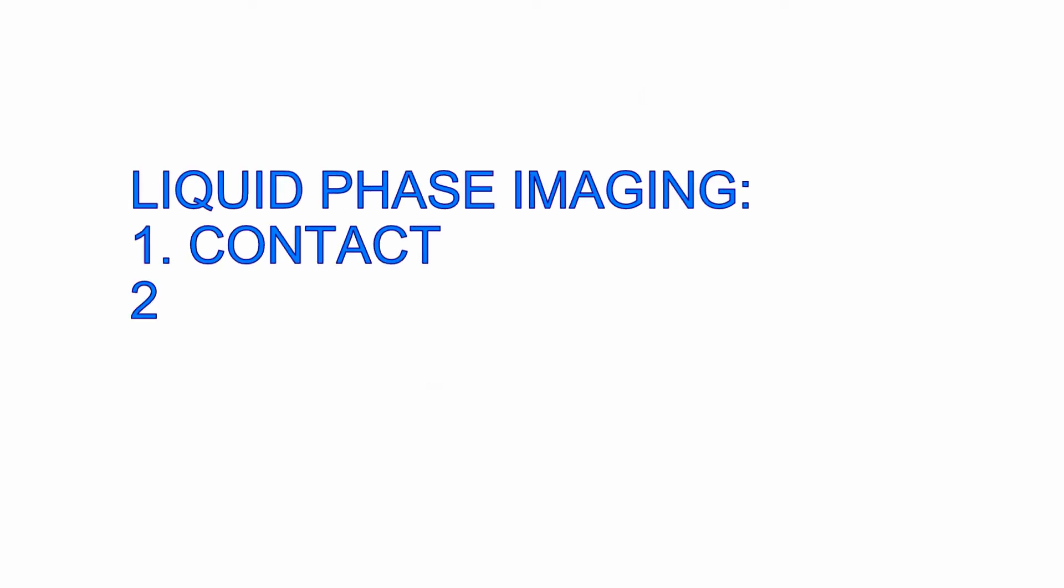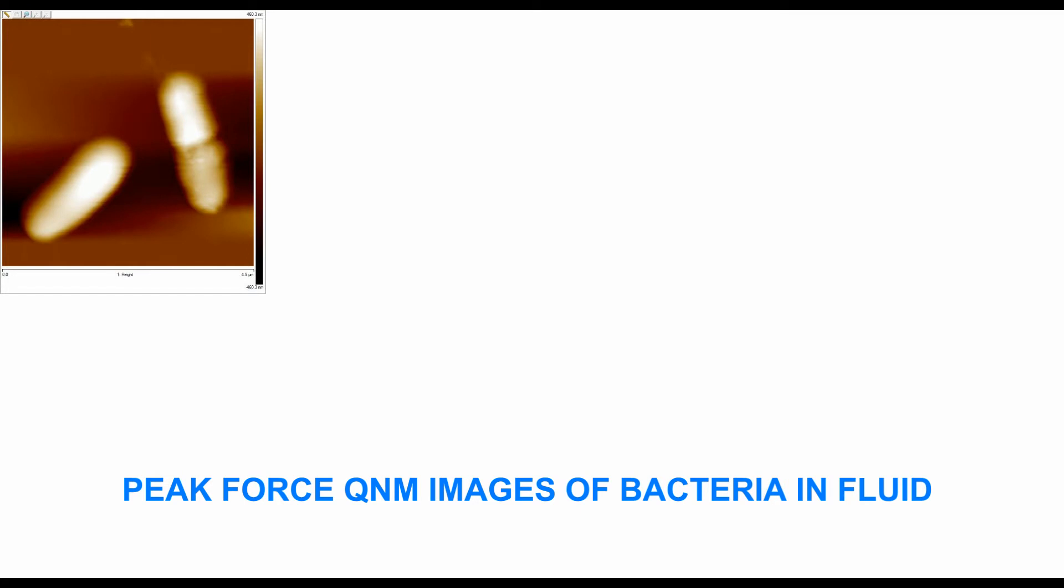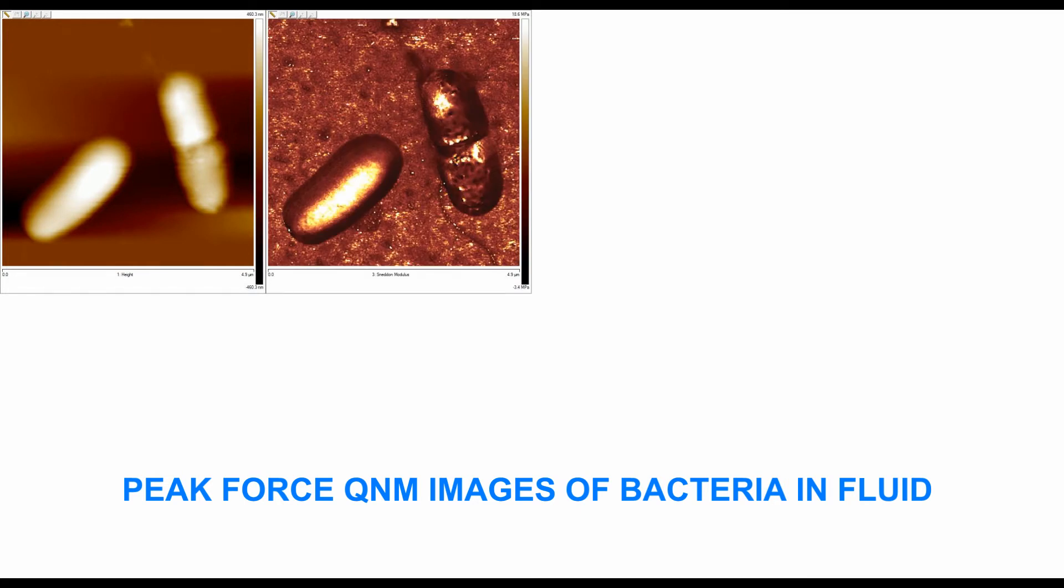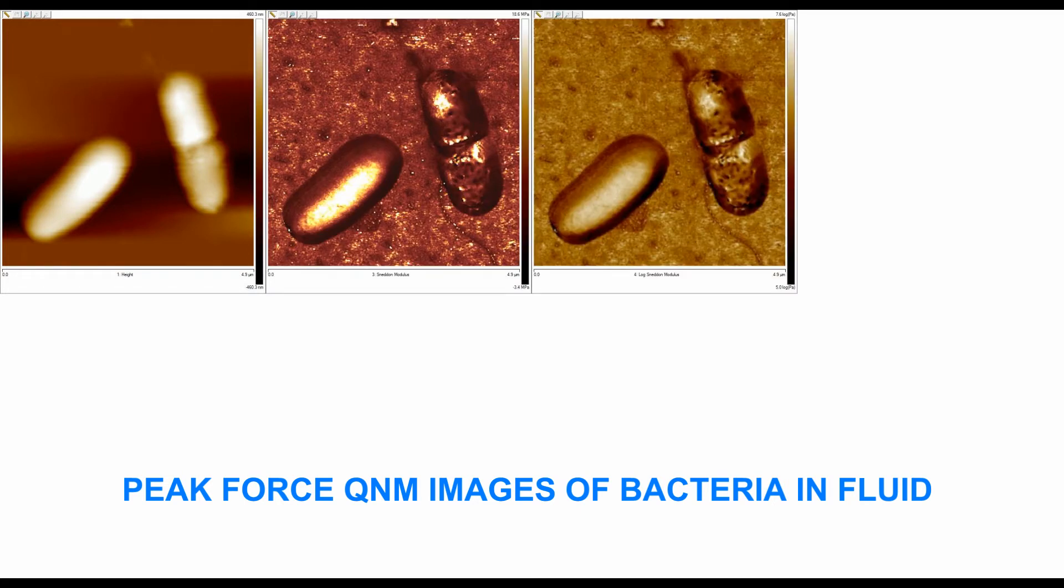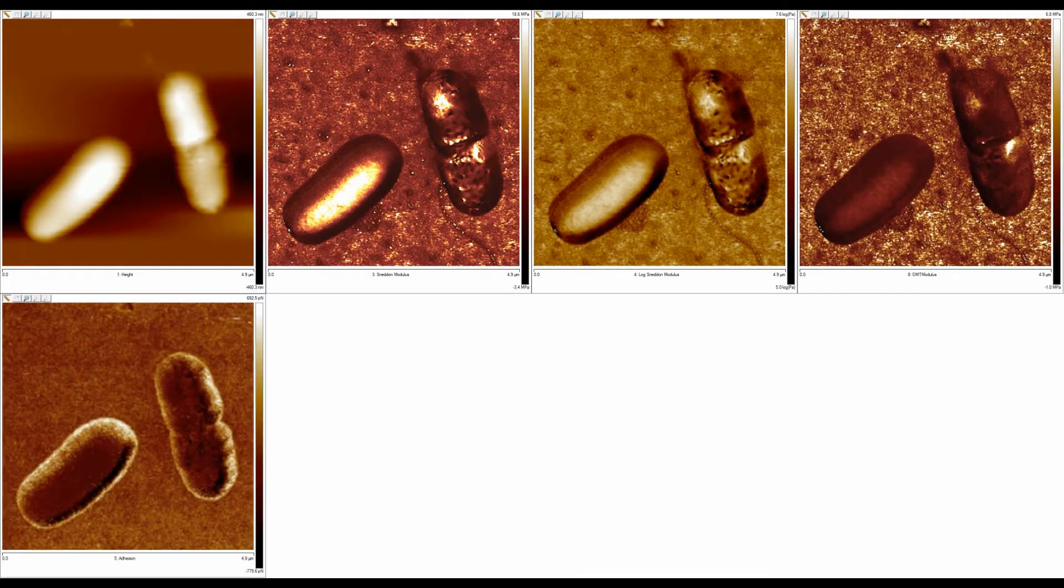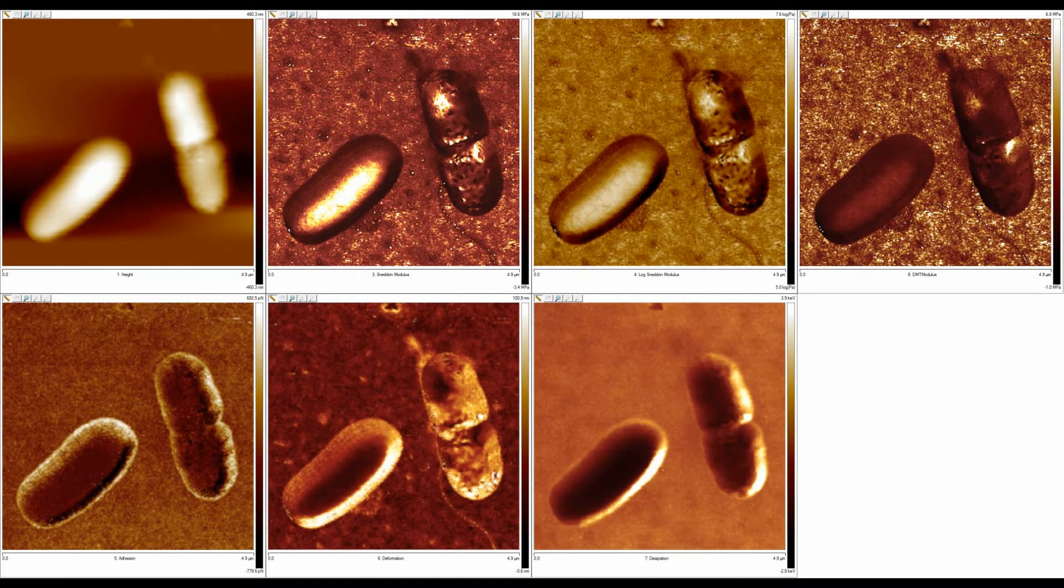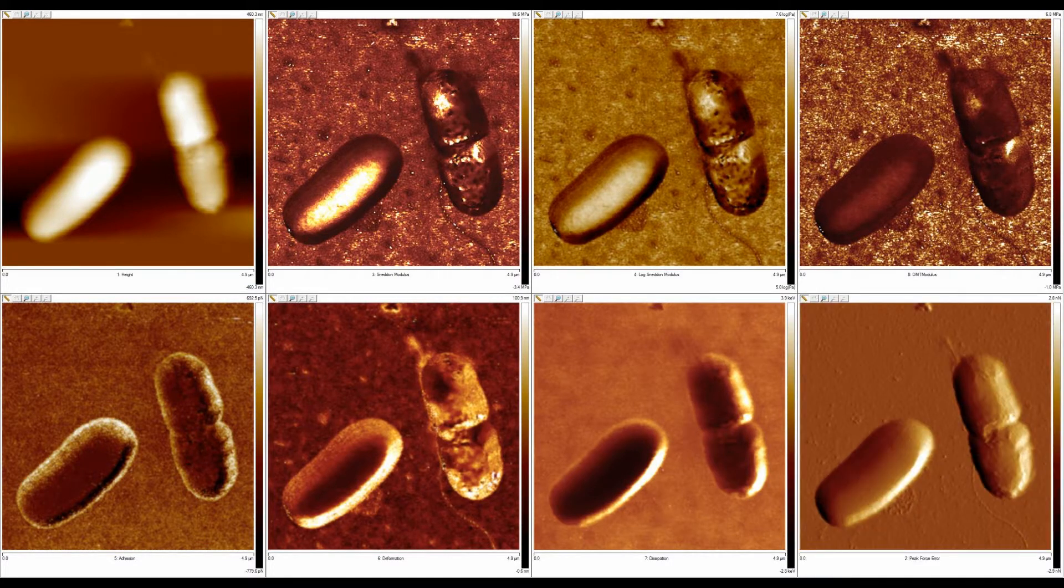All three primary imaging modes—contact, tapping, and scan assist—can work in fluid. Contact mode is not used as often because it is heavily influenced by shear forces. Previously, tapping mode was the dominant mode used in fluid imaging, but tuning the cantilever in fluid can be difficult because the liquid inhibits the free motion of the cantilever. Peak force tapping mode is an intermittent contact mode that eliminates the shear force problem.